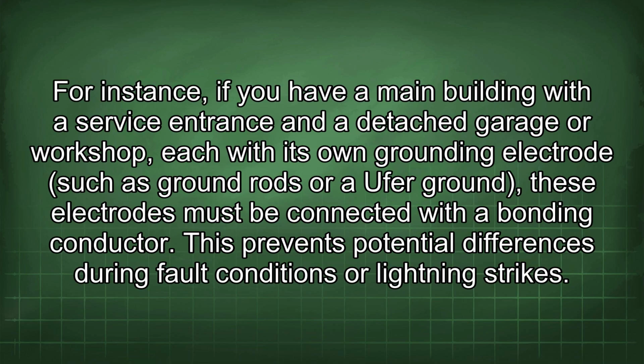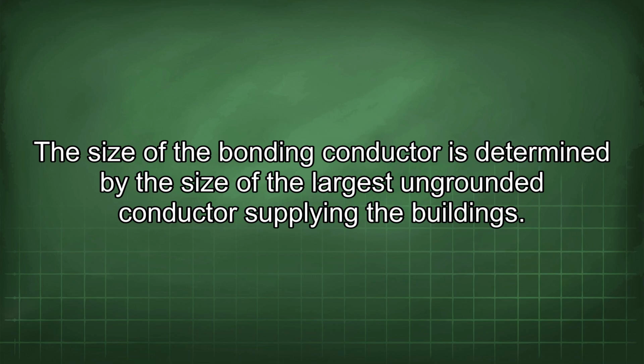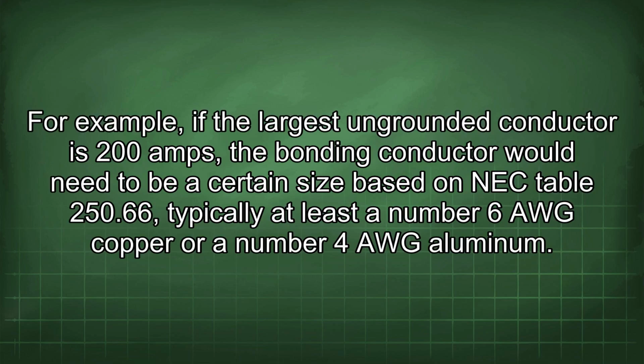For instance, if you have a main building with a service entrance and a detached garage or workshop, each with its own grounding electrodes such as ground rods or a Ufer ground, these electrodes must be connected with the bonding conductor. This prevents potential differences during fault conditions or lightning strikes. The size of the bonding conductor is determined by the size of the largest ungrounded conductor supplying the buildings. For example, if the largest ungrounded conductor is 200 amps, the bonding conductor would need to be a certain size based on NEC Table 250.66, typically at least a number 6 AWG copper or a number 4 AWG aluminum.